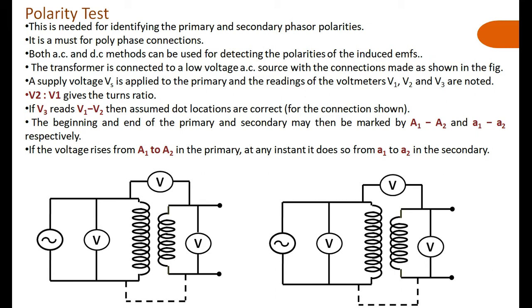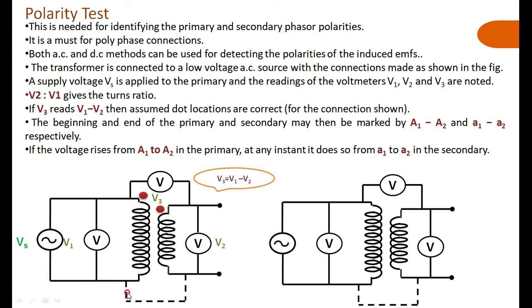The transformer is connected to a low voltage AC source with the connection made as shown in the figure. The LV side is connected to the supply voltage Vs. You apply a small voltage, and as you can see in the connection diagram, between the primary and secondary you connect one voltmeter across the terminals. One of the terminals of the primary and secondary are short-circuited.